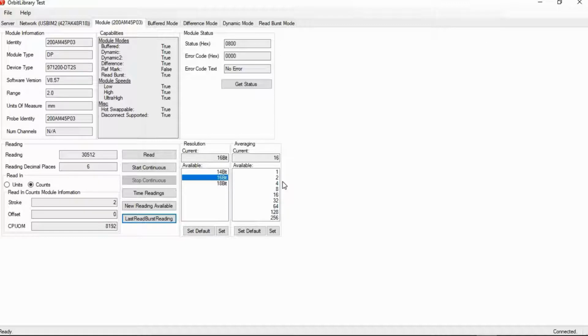Now, another way we filter that signal is through averaging the data from the A to D converter. By default, it is set to 16 samples. This is more than sufficient for dynamic or static situations. But if you are doing, say, a long-term test, such as monitoring a crack on a bridge over several days or several months, you can actually increase the averaging to 256 if you would like, which prevents transient changes showing the overall trend of measurement.